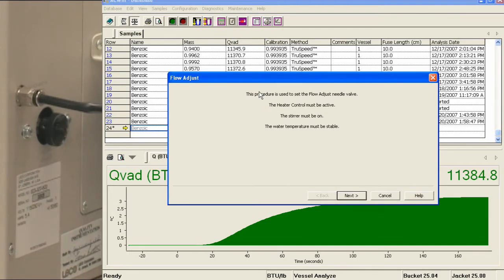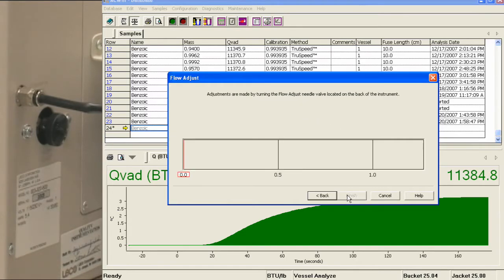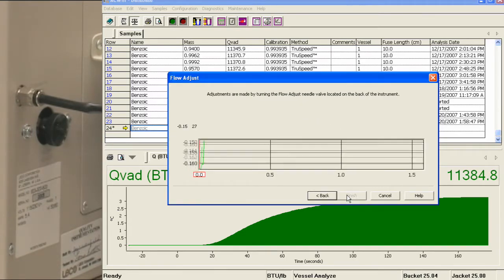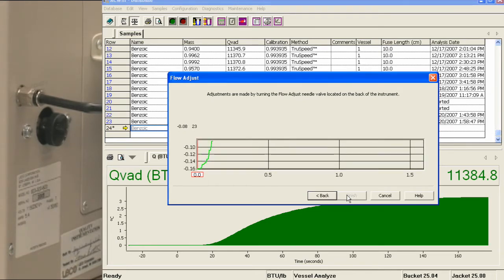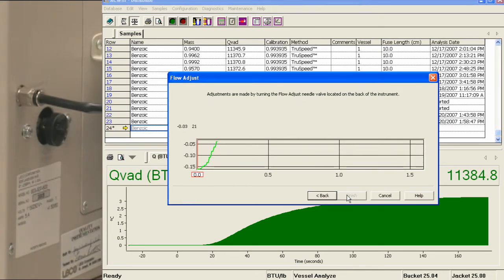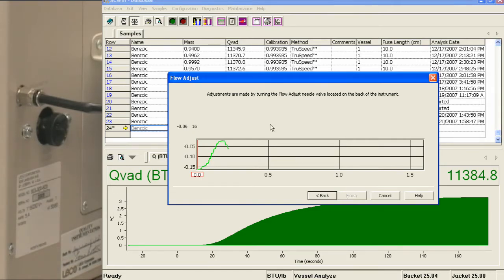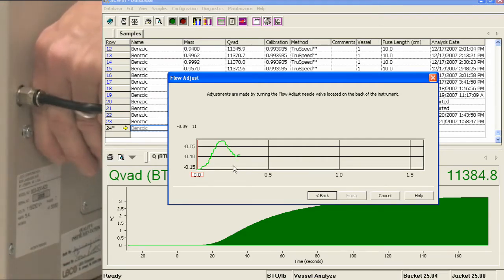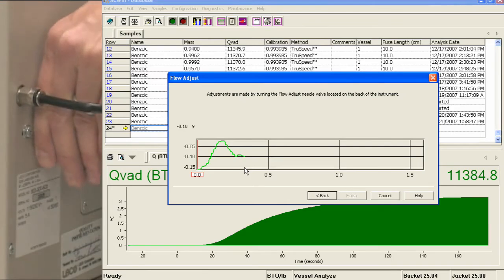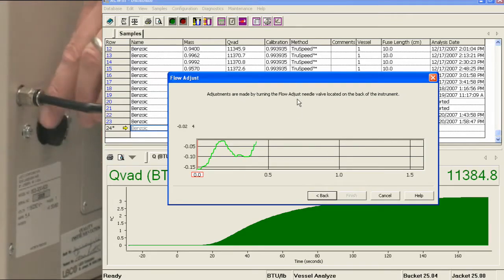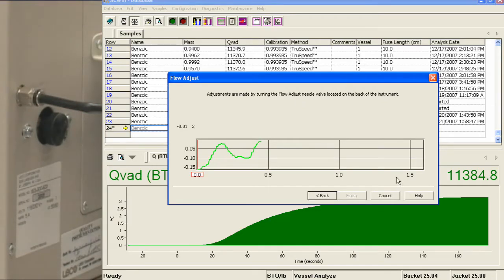You'll press next on the screen, and it will give you a series of instructions to follow. It will tell you whether to rotate the flow adjust needle clockwise or counterclockwise. You're trying to reach a target of 0. If it's red, you're too high with your duty cycle. If it's black, you're too low. How you adjust your duty cycle is by adjusting the flow. You have a flow controller on the back of the instrument. So in order to adjust that, either way, you follow the instructions that are given by the computer to see that you have adjusted the duty cycle appropriately to get down close to 0.